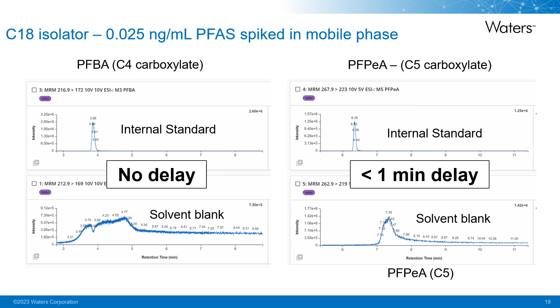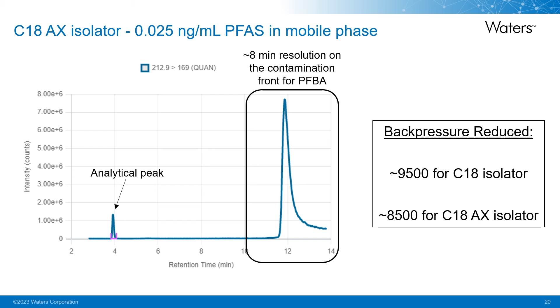But if we do nothing else but change that reverse phase C18 only isolator column to the C18AX mixed mode column as an isolator, it actually provides us 8 minutes of resolution on the contamination front for PFBA from the analytical peak, which is a far cry from what we saw on the previous slide. One of the added benefits that we found for using this column as an isolator is that we can select a larger particle size to decrease some of the back pressure contributed from putting that additional column on the system. So it gives us a little more room in our gradient and what type of gradient we can run by having a lower back pressure.